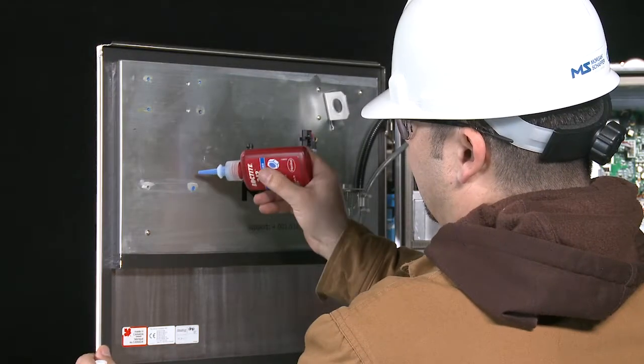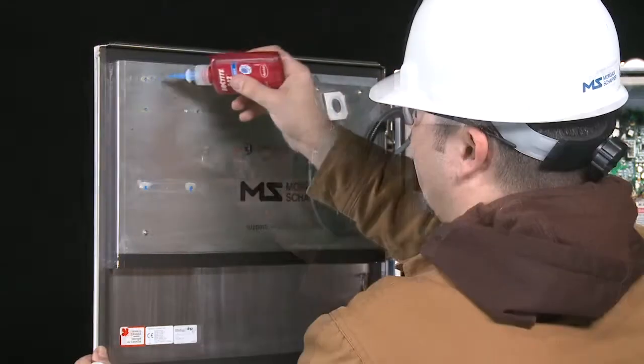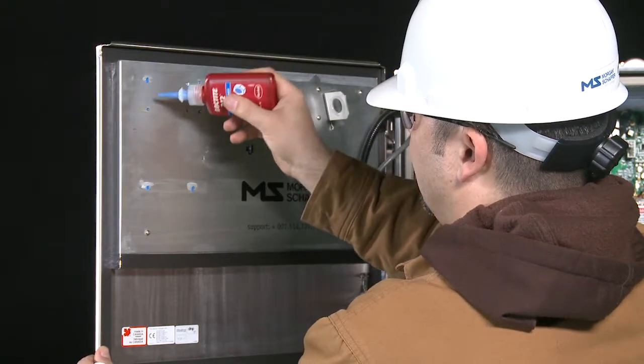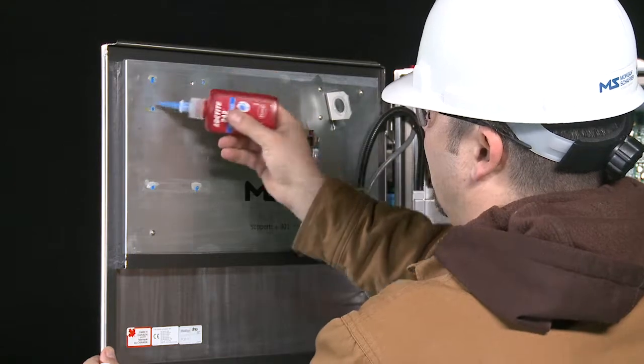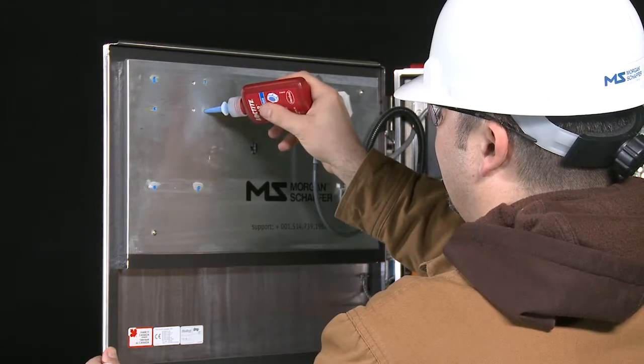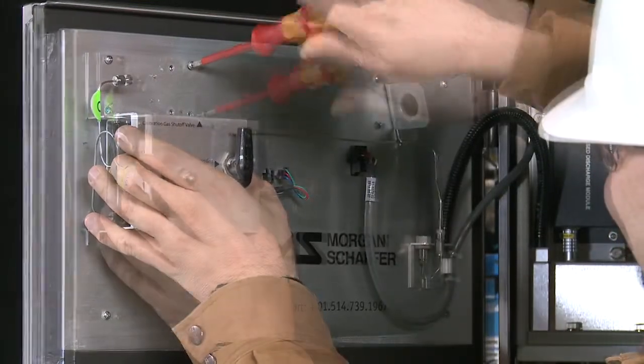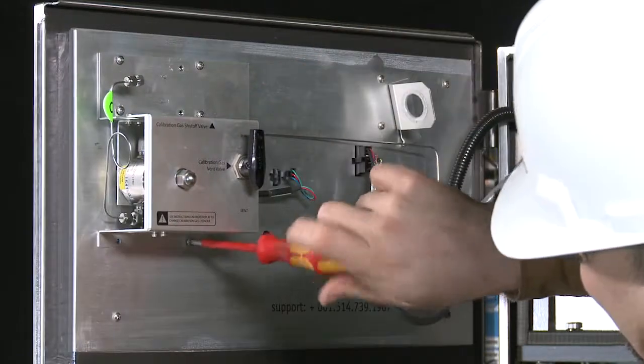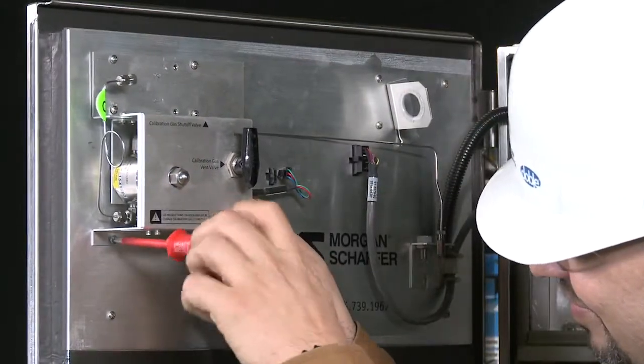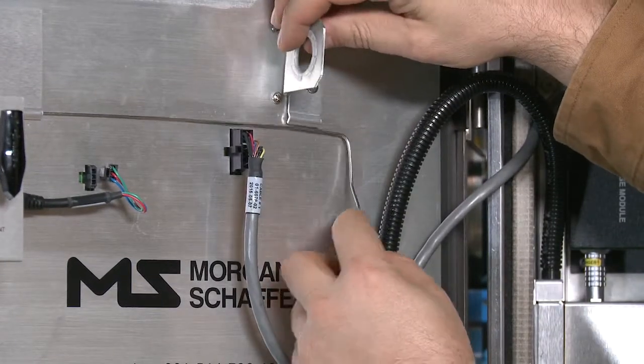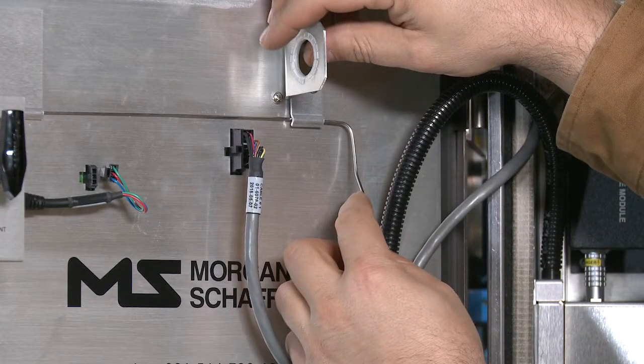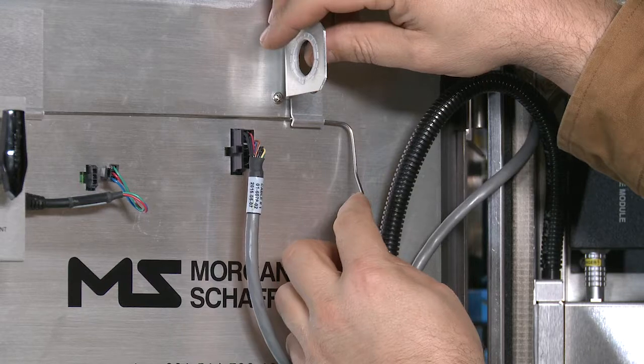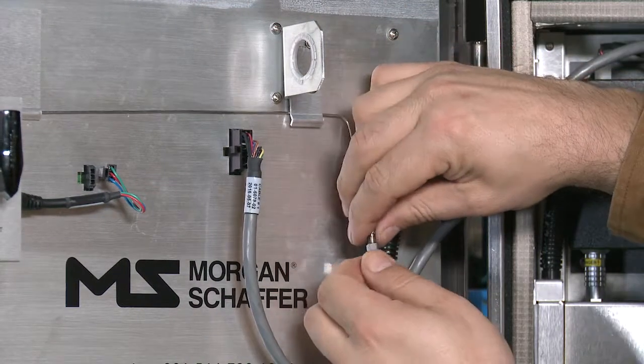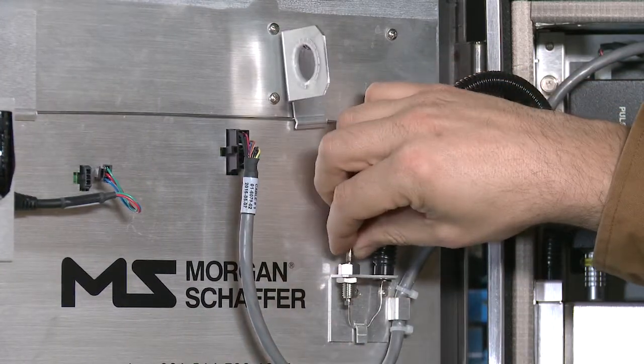Installing the calibration gas module. Apply thread locker on the 6 threaded holes on the door. Install the new calibration gas module by partially tightening the 6 screws using a Phillips No. 2 screwdriver. Place the calibration tube under the cylinder retainer. Be careful not to pinch the tube between the retainer and the door. Connect the new calibration gas module pressure sensor cable on the connector located in the middle of the panel.